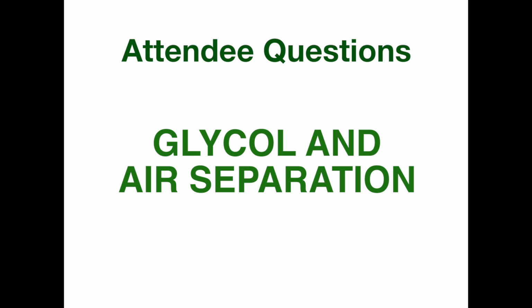Also, glycol is very viscous compared to water, and it prevents the bubbles from wanting to migrate up as quickly as they would in water. As a result, they have a higher tendency to carry through a separator. And resultingly, oxygen will spend more time in a glycol system. And of course, glycol scavenges oxygen, and that's why glycol manufacturers will typically include an inhibitor with their glycol. So probably more than was needed to know, but I just wanted to explain that because there were 3 or 4 questions that came in on that.